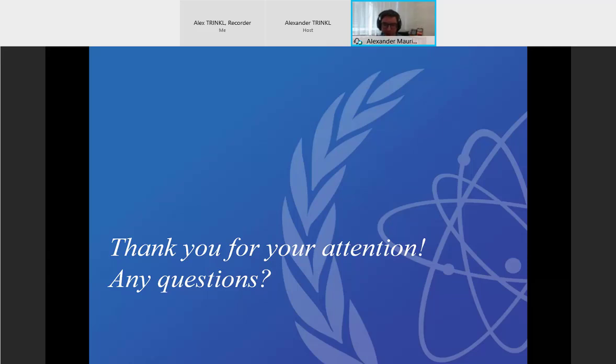I would say energy calibration, it's so easy to do. I will recommend everyone to make a general energy calibration, so you really have the full picture of the relationship between channel and energy. To do the comparison directly between a standard with a certain nuclide and compare that to the sample of a certain nuclide, that is a very acceptable way of doing it, but you need to make sure that the sample and standard are geometrically or physically the same, or at least very similar. If not, there could be geometric differences that would create an error if you don't correct for it.